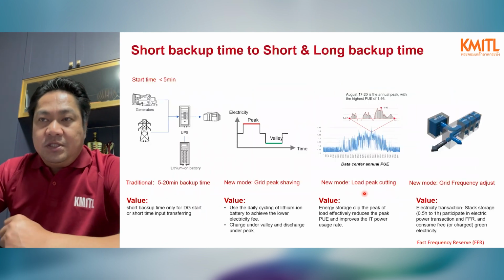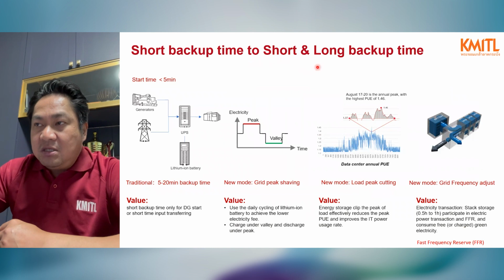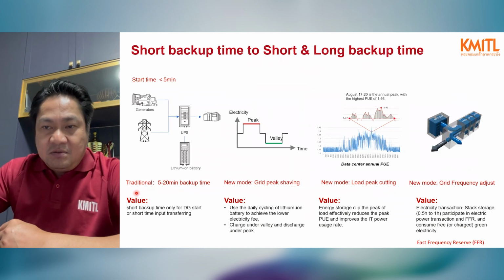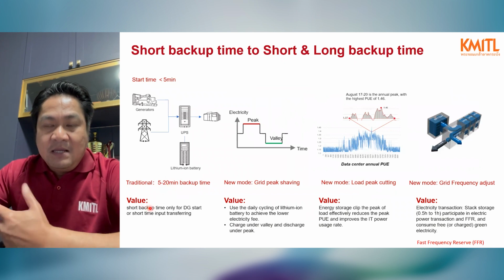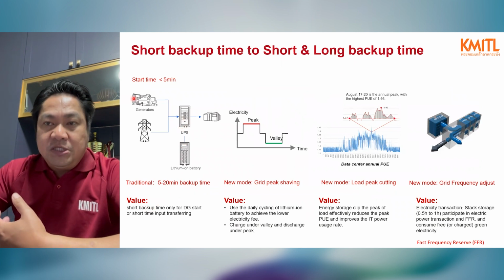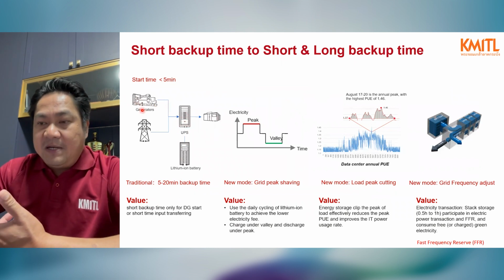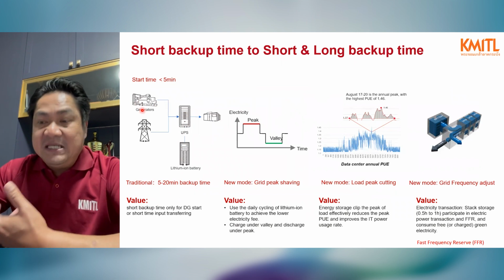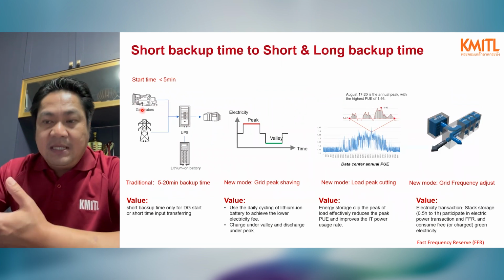So we come to short and long backup time. Traditional backup for 5 to 10 to 20 minutes means they are used to back up while waiting for a generator to start up and then supply the load. The generator can take about 15 seconds to start up, so the battery can handle that first period.